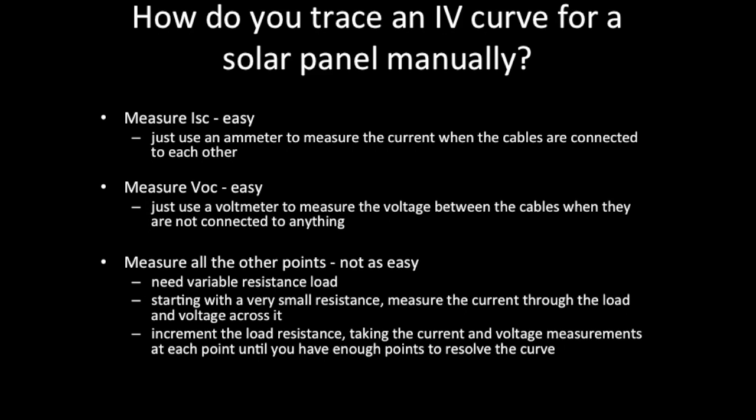Before we talk about the IV Swinger, how do you do this manually? Measuring the short circuit current ISC is easy — just connect the cables together directly and use an ammeter to measure the current. For VOC, the open circuit voltage, that's also easy — just connect a voltmeter across the cables when they're not connected to anything and the reading you get is the VOC.